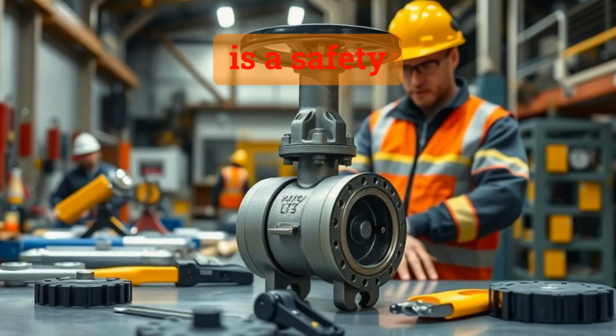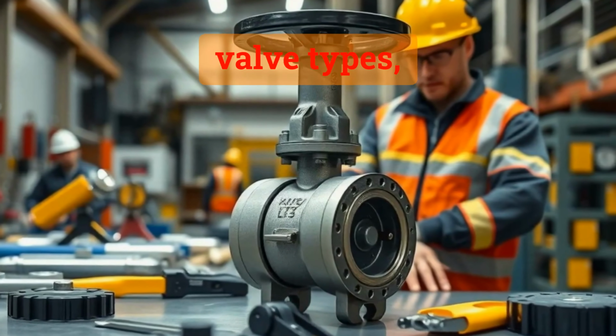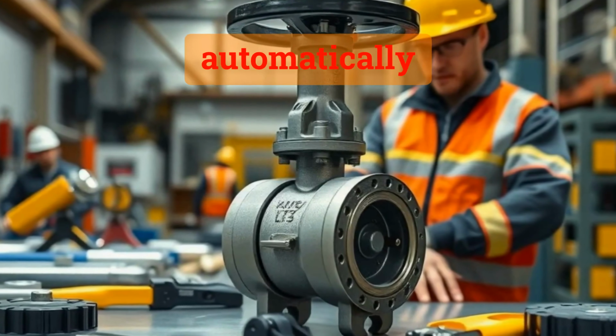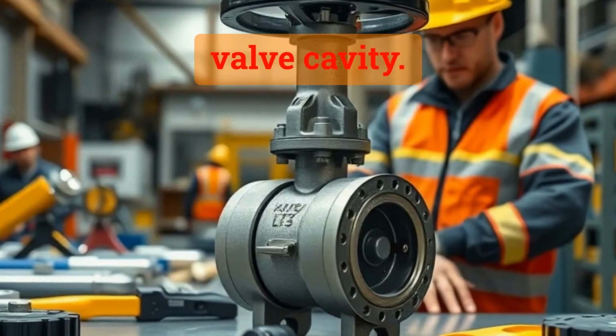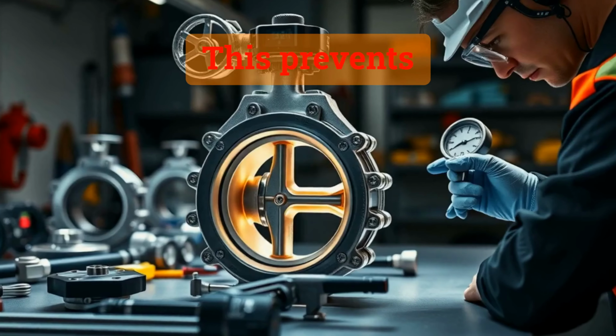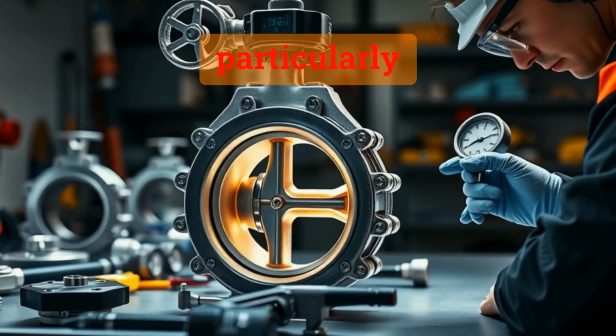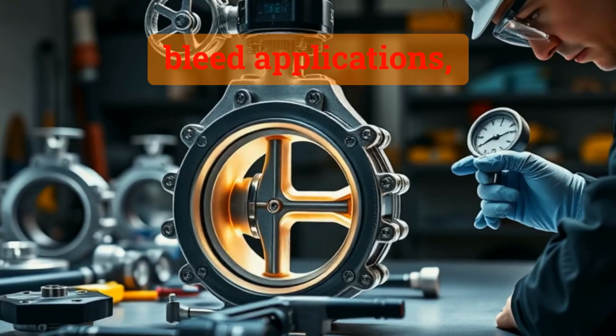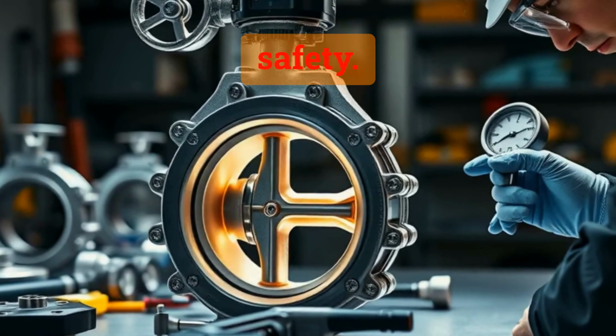Self-relieving seat design is a safety feature in certain valve types, such as ball valves, that automatically releases excess pressure trapped in the valve cavity. This prevents dangerous pressure buildup, particularly in double block and bleed applications, and contributes to overall system safety.